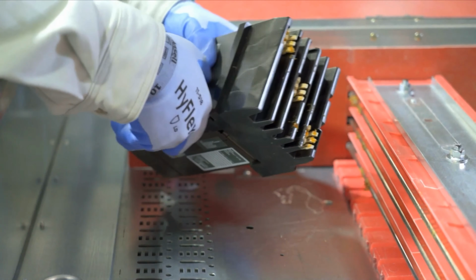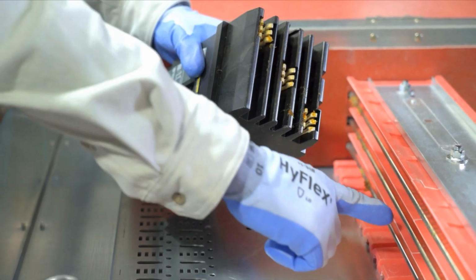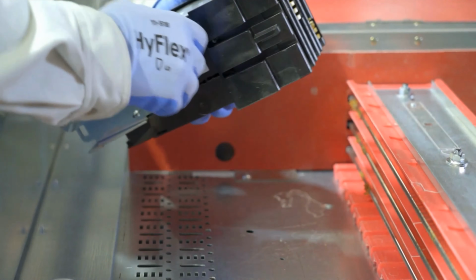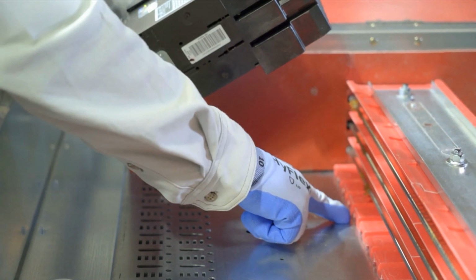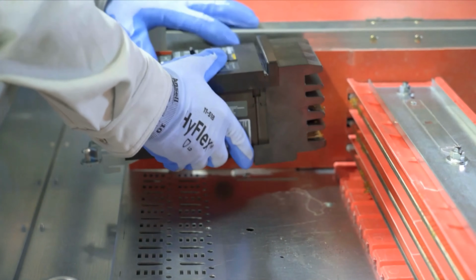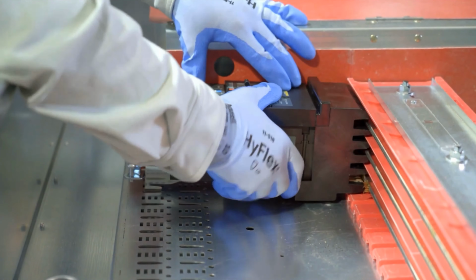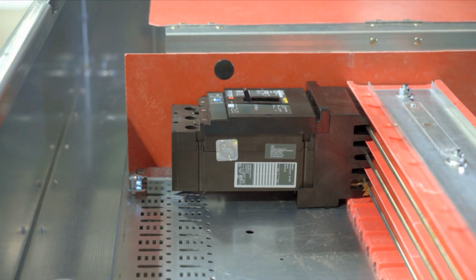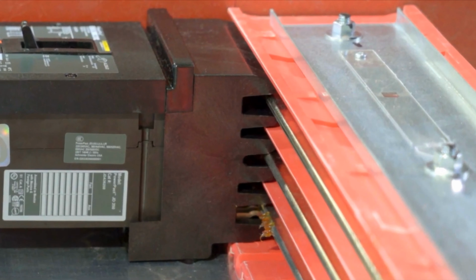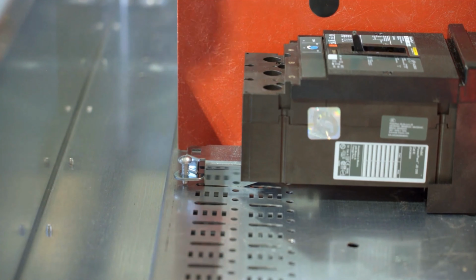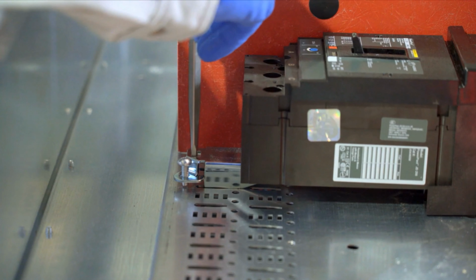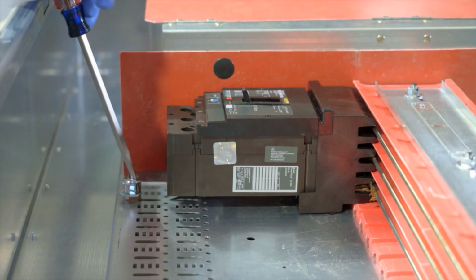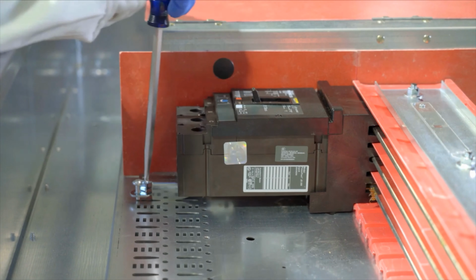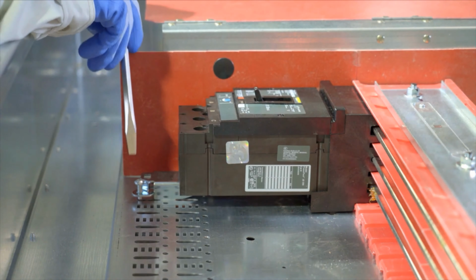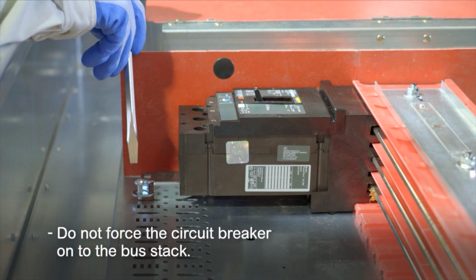To install the circuit breaker, position the circuit breaker jaws against the bus bar stack so that the key slot on the bottom of the circuit breaker is oriented towards the alignment groove in the bus insulation base. And make sure the fingers of the circuit breaker mounting bracket fit into the key slots in the pan. To complete the install of the circuit breaker, place a screwdriver through the rectangular hole in the circuit breaker mounting bracket and into the screwdriver slot in the mounting pan. Ratchet the circuit breaker firmly into the bus bar stack and align the retaining screw with the mounting hole in the pan. Do not force the circuit breaker onto the bus stack.